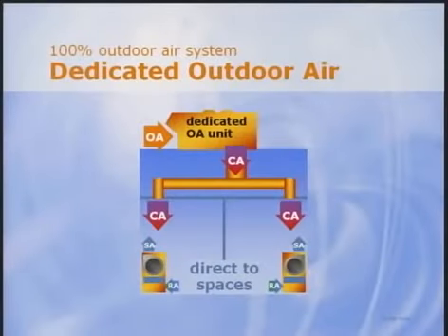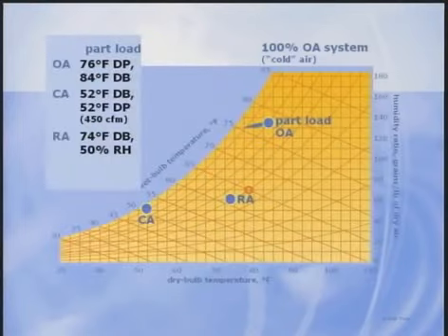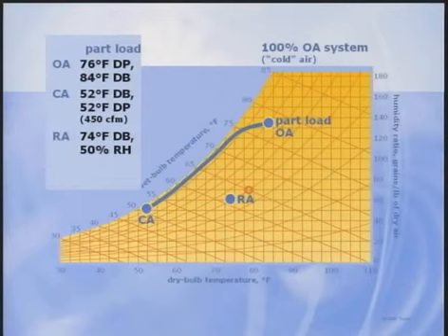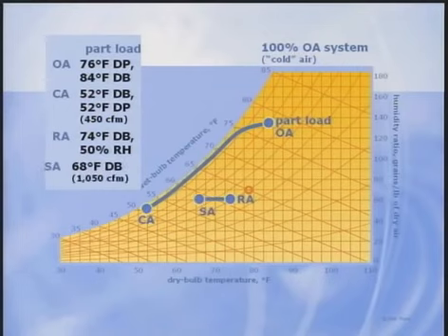It seems that a lot of designers these days want to decouple the latent load from the sensible load using a dedicated outdoor air unit in a 100% outdoor air system. One air handler dehumidifies all of the outdoor air while local units handle the sensible load in each zone. If the outdoor air delivered to each zone is dry enough, it prevents high zone humidity. An iterative psych chart analysis at the design dew point condition shows that if the outdoor air is delivered to the zones at 52 degrees and the local unit delivers air at about 68 degrees, these two air streams mix in the zone to keep the relative humidity at about 50%.